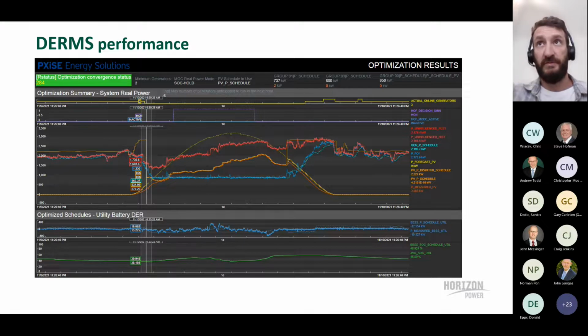The top plot shows how many generators are online, and the second plot uses predictive analytics in DERMS to indicate when a hydrocarbons-off decision could be made, meaning all generators go off and we run at 100% renewable energy operation. That purple trend indicates about 7 to 8 hours of HOF period we could have run if commissioned, which we're actively working on.